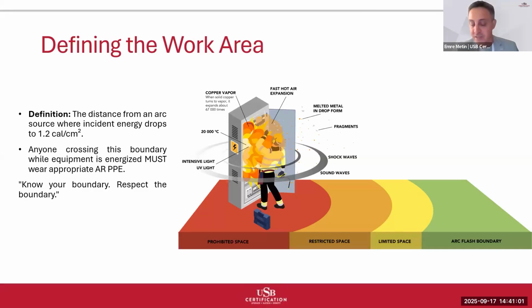The boundary also defines different zones with different requirements. Arc flash boundary, minimum distance for unprotected persons. Limited approach boundary, shock protection requirements begin. Restricted approach boundary, enhanced shock protection required. Prohibited approach boundary, only qualified persons with specific training and PPE. The key message: know your boundary, respect your boundary. These aren't arbitrary administrative requirements. They are engineered safety distances based on the physics of electrical hazards.